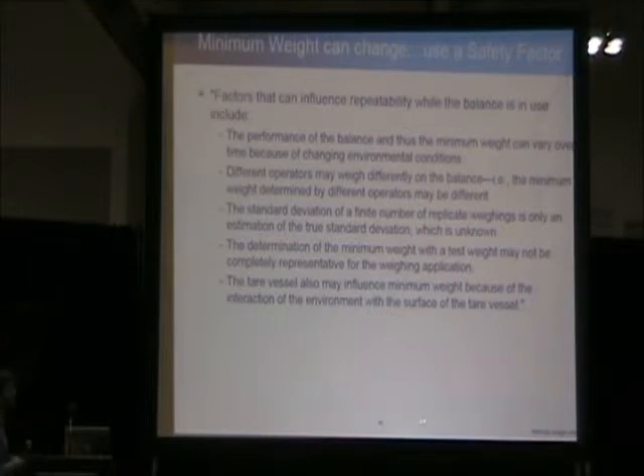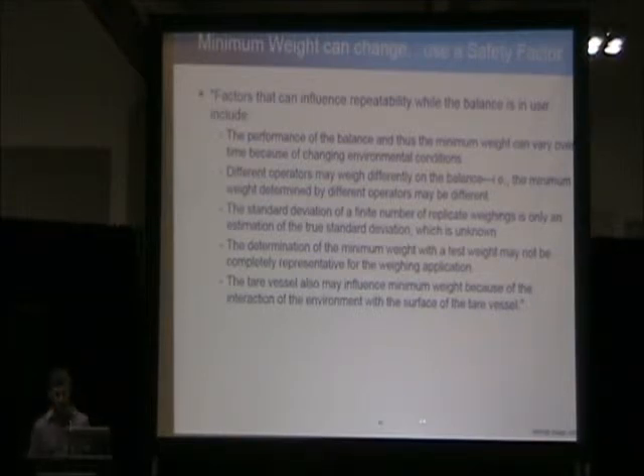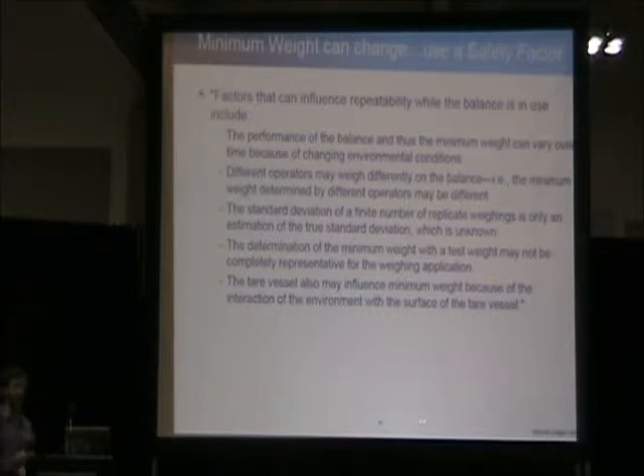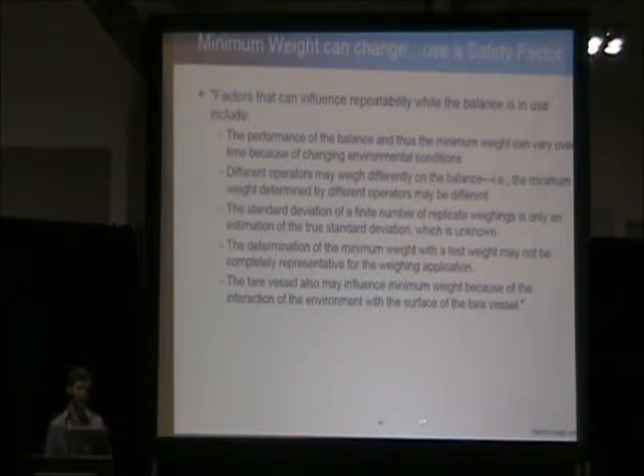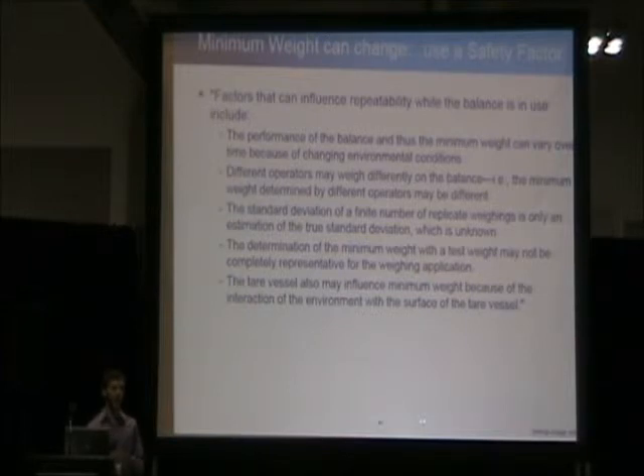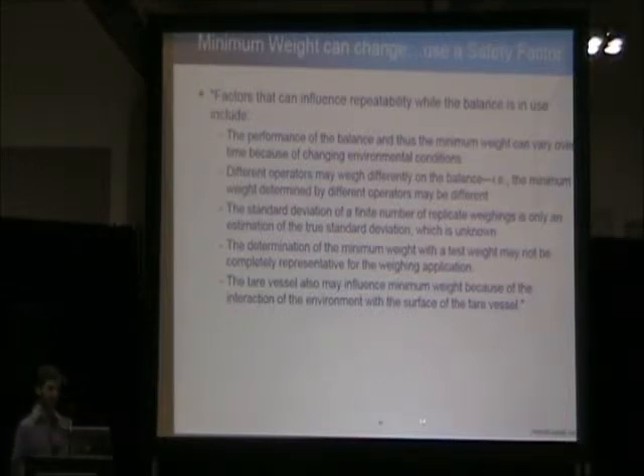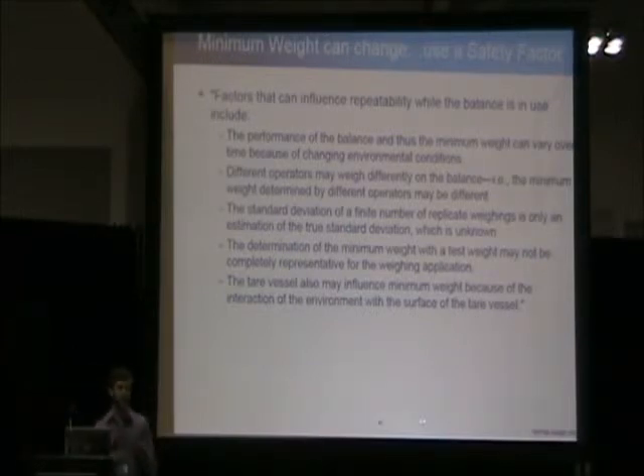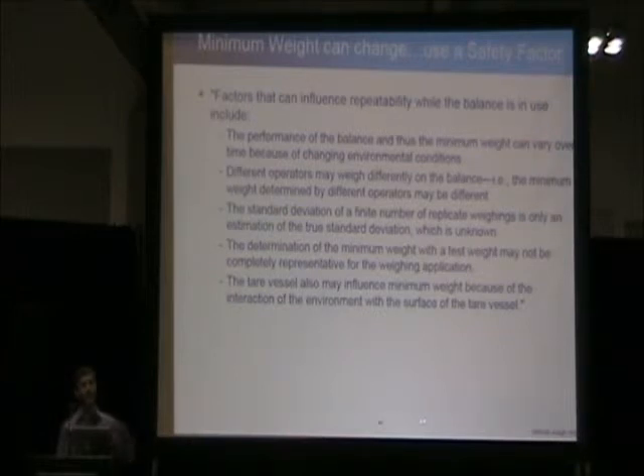Also, the standard deviation of a finite number of replicate weighings is only an estimation of the true standard deviation, which for all weighing instrumentation is unknown. When you determine the minimum weight with a test weight, which is stainless steel, you actually are going to achieve more than likely a better minimum weight than when you're weighing sample. When you weigh powders, as an example, which are very static, that static on that powder is going to increase your uncertainty of measurement. Stainless steel masses aren't going to have a lot of static forces on them. So when you perform your repeatability test with a calibration weight, you're actually going to achieve more than likely a lower minimum weight than when you would by doing any sort of normal, everyday laboratory weighing.